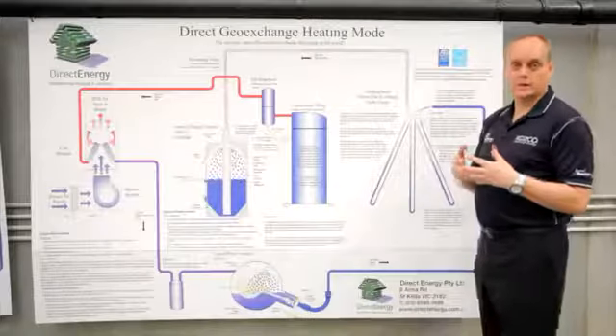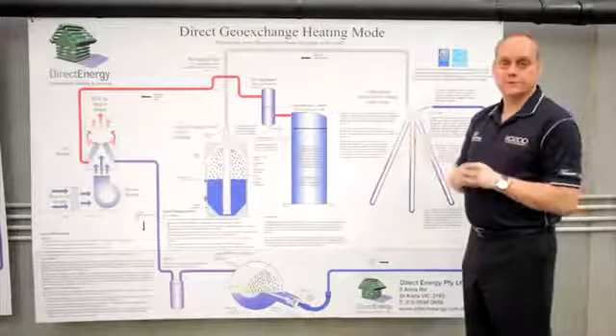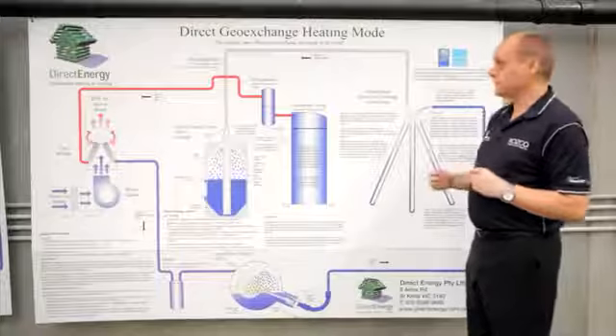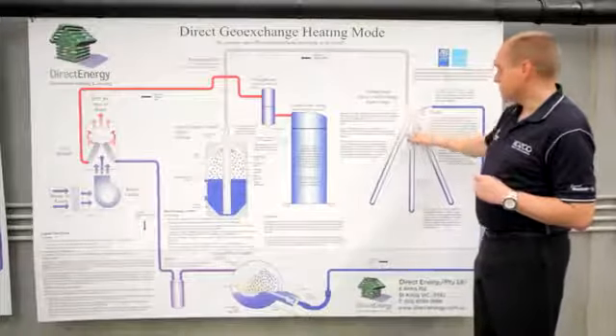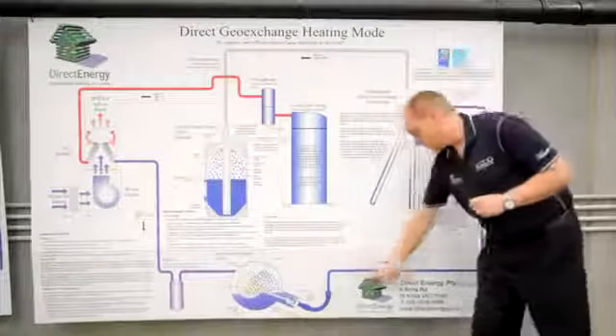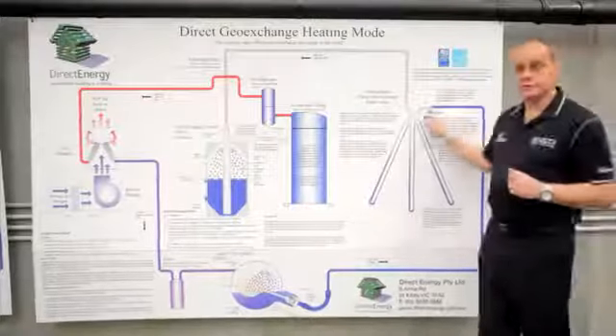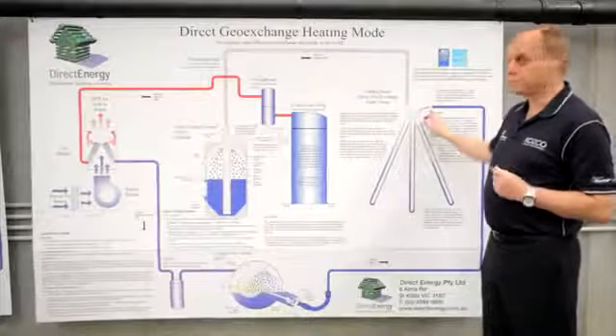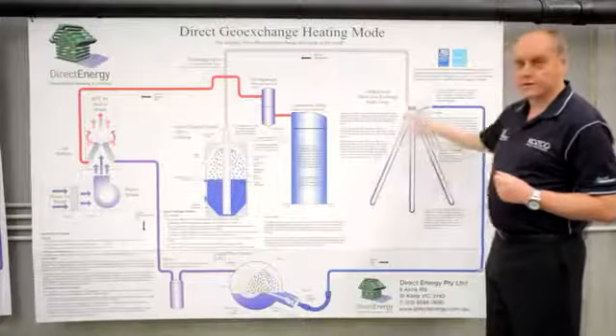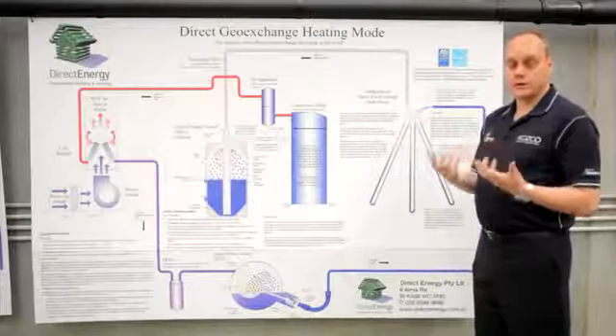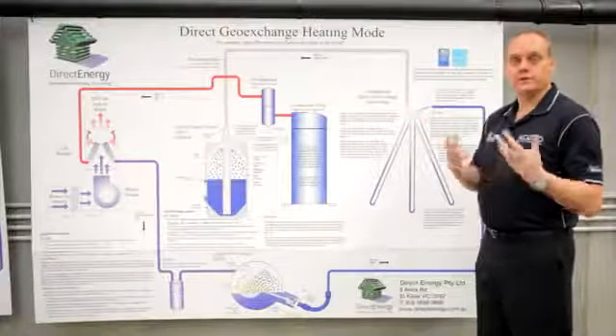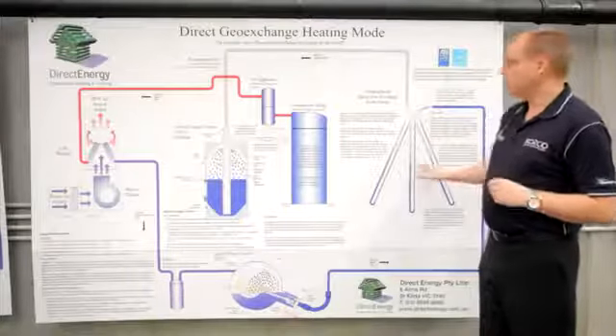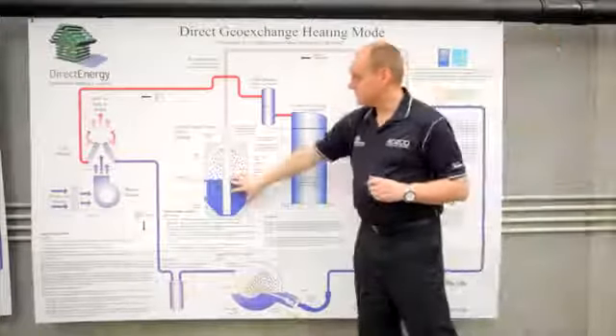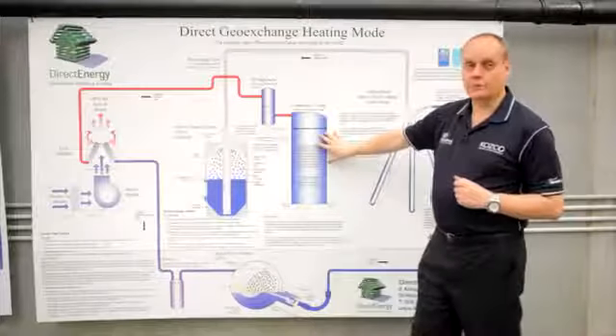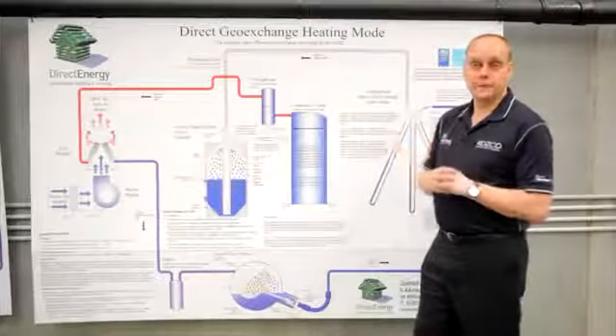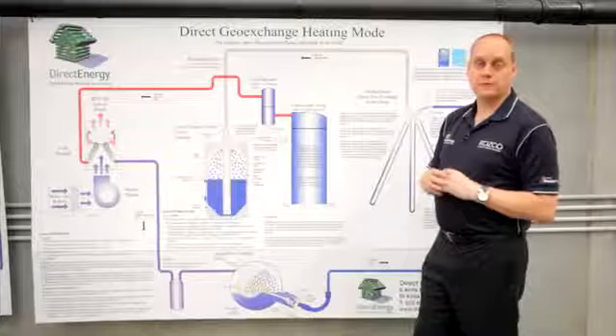and obviously we would like to use the ground to transfer energy into the refrigerant to heat it up so that it can be preheated to go into the compressor. In this system we're demonstrating that the liquid is coming back to the earth loops at a little bit less than 2 degrees Celsius. The earth loops will allow the constant ground temperature of the earth to evaporate the refrigerant off into a vapour state.